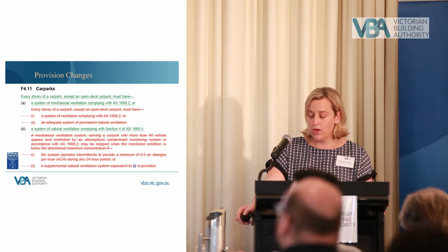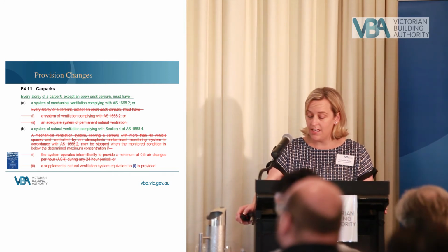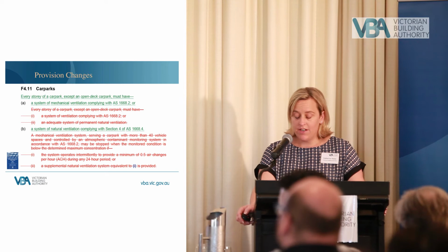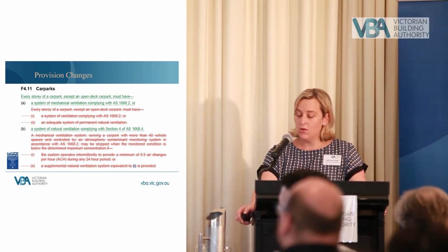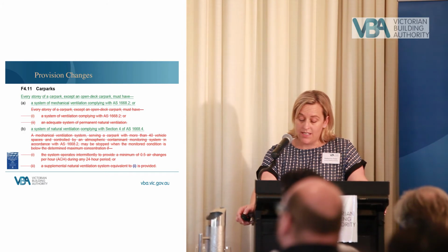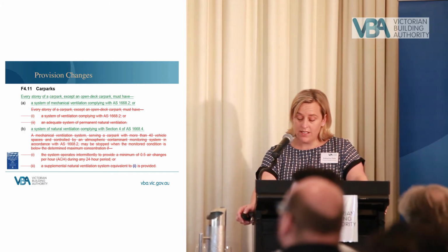F4.11 also previously required some background ventilation to always be provided in circumstances that a car park exhaust system was deactivated by an atmospheric contaminant monitoring system.